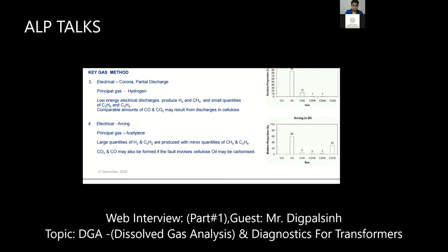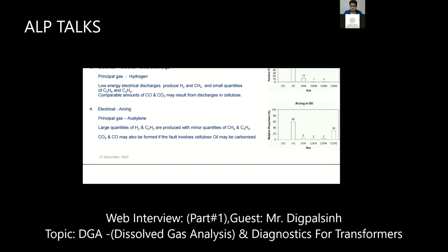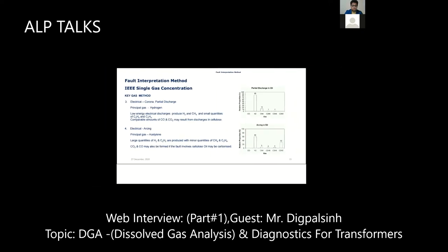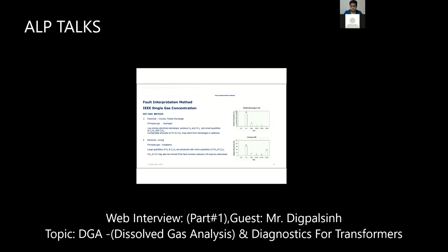In case of arcing, you will get large quantities of hydrogen and acetylene, with minor quantities of methane, ethane and ethylene, C2H4. CO2 and CO will be formed if cellulose is also involved. Your arcing will be near your cellulose, but it will be discharged partially. Partial discharge is there, so by tracking or the tree effect, your cellulose will be damaged, and it will produce CO2 or CO. These are the basic IEEE single gas concentrations.